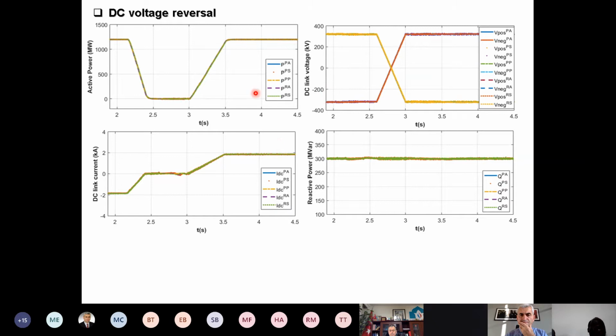And you can see here, because we maintain the power flow constant with the change of DC voltage, the DC current polarity has to change. This means if we kept the DC current fixed, positive or negative, then the active power will change. So this example clearly shows that in the full bridge MMC, we can change the power flow either by DC voltage change, or by change of polarity of DC voltage or change of the polarity of DC current, while the reactive power remains unaffected over the entire period.